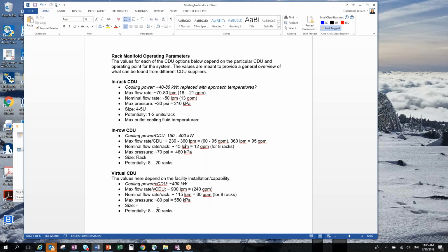Yeah, but maybe we're keeping that out then. Maybe not, because it's facility dependent. Maybe we're making too big of a scope if we include that, since we're making assumptions here. Coming back to my previous comment, if you looked at this at the rack level, what's the pressure actually needed to move fluid through a manifold serving a certain amount of IT equipment? That's the pressure we really need. We don't care about the pressure output of the CDU, we care about the manifold pressure.